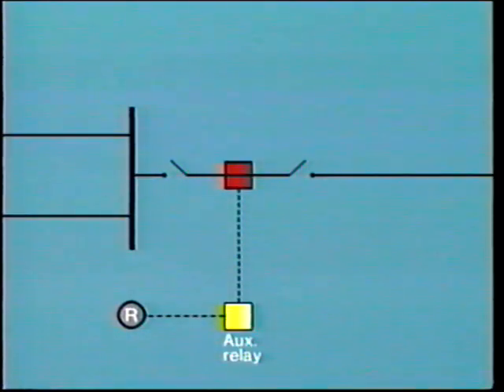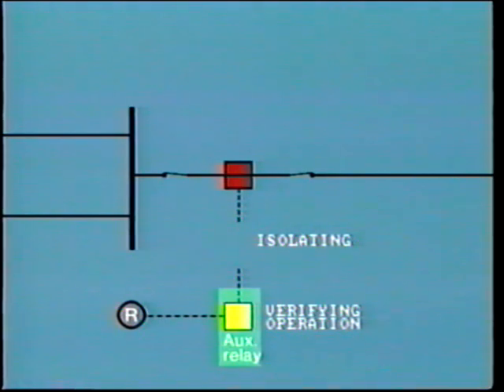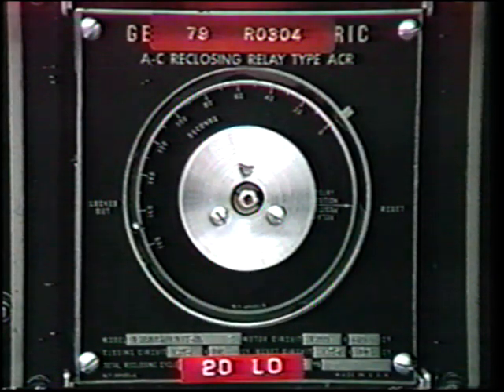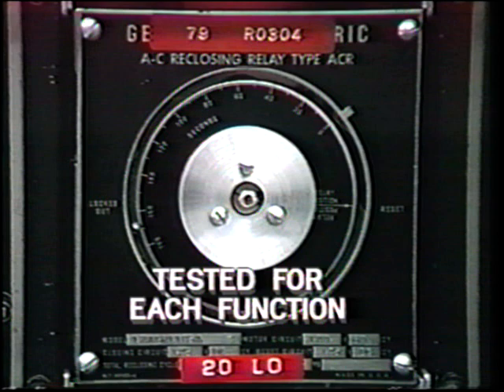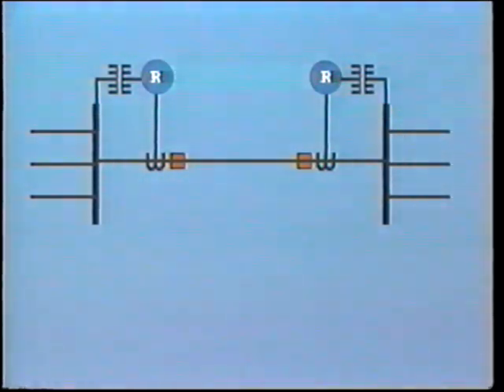Once this test has assured that the breaker trips from the auxiliary relay, further testing of protective packages can be performed by isolating the breaker trip circuit and verifying operation of the auxiliary relay only. This method will reduce wear and tear on the breaker. If an automatic reclosing relay is installed on this circuit, this must also be tested for operation at this time. The reclosing relay should be tested for each of its different program functions, that is, its different time settings. Operational tests should also include the sending and receiving of appropriate communication signals for pilot schemes or direct transfer trip.